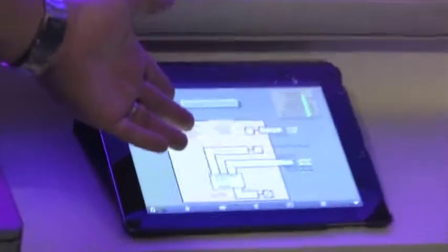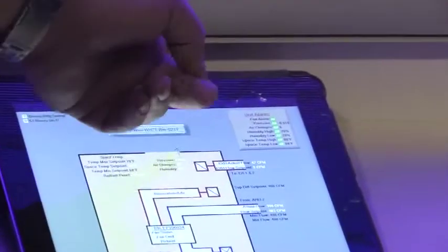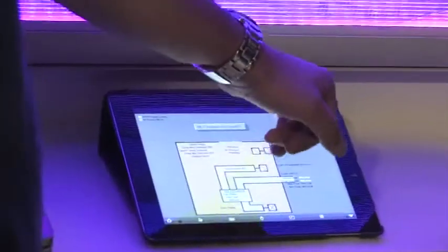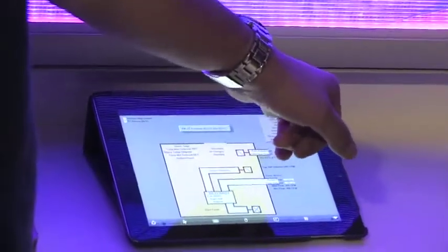So like I said, you have your set point adjustments, your humidity high-low, temperature high-low set points, your pressure alarm set point, your air changes, and a fan alarm. So if the fan fails, you'll get an alarm on that, unlike the VAV box that obviously doesn't have the fan in it. But the VAV and these are going to be all controlled the same way, minus the fan.